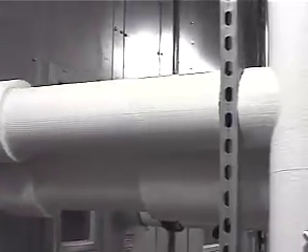As you go down these, you have your different coils. This is your chilled water coil. You just have your averaging element that runs down the side of it. It's just there for monitoring purposes to let you know what kind of delta T you're getting. We don't have isolation going into the air handler, right? Or is there isolation on this side? Okay, there's some up there. Same thing on the other side for your indirect.